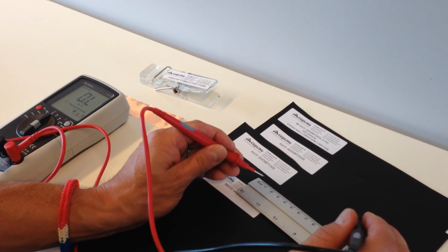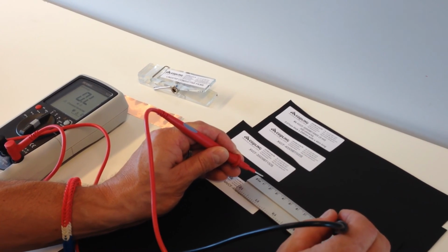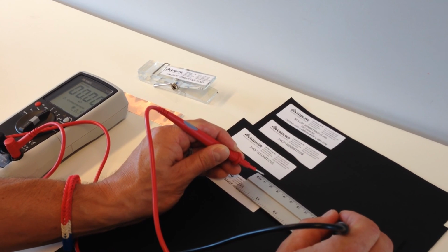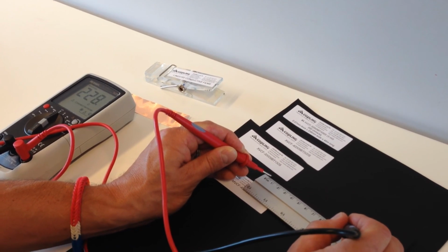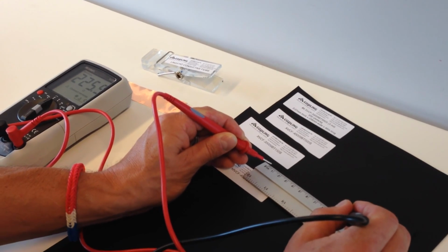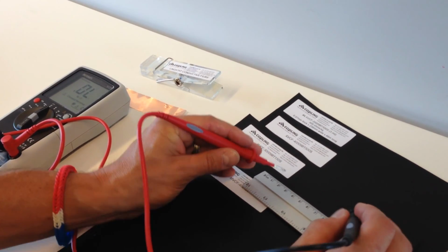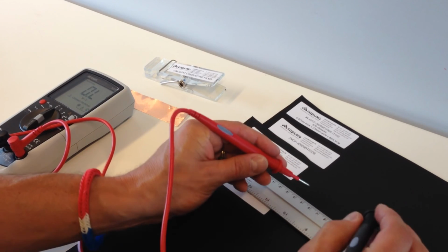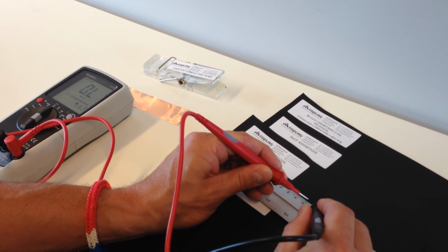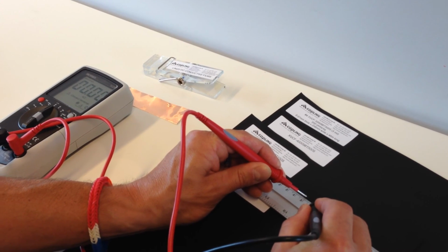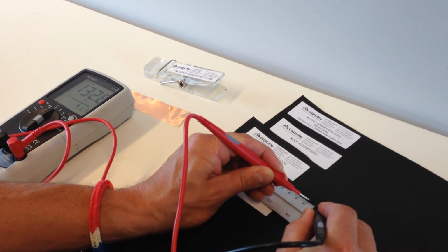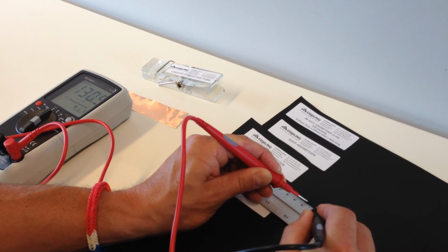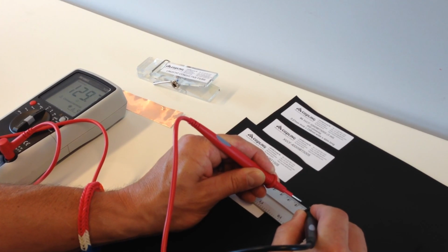Again, the values that we test are the values at 10 centimeters, and here you see that the value comes to about 227. But the value that we actually record on the data sheets is a value that's 1 centimeter apart. If you look at 1 centimeter apart, what we end up with is 133, 135, and the values are close to 150.